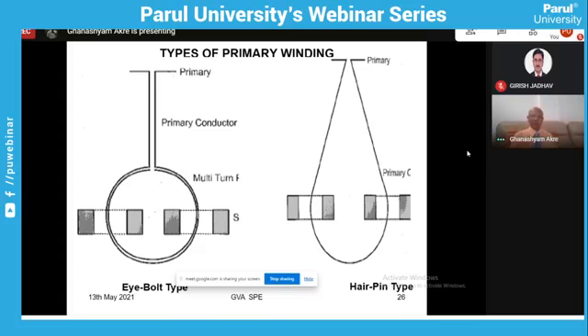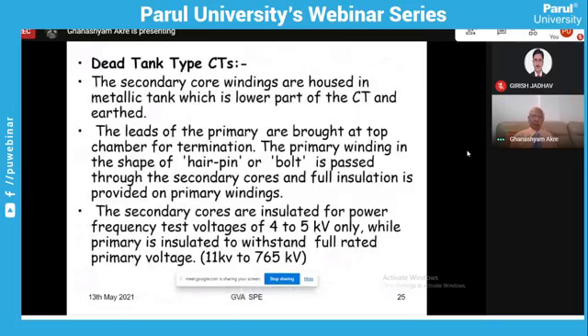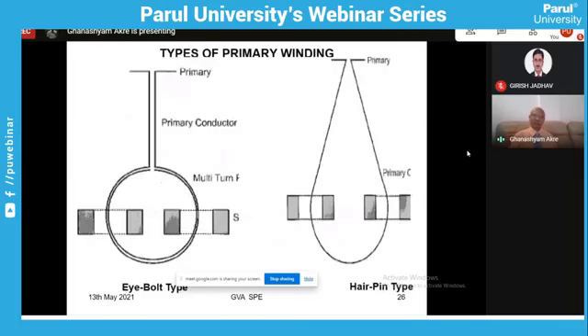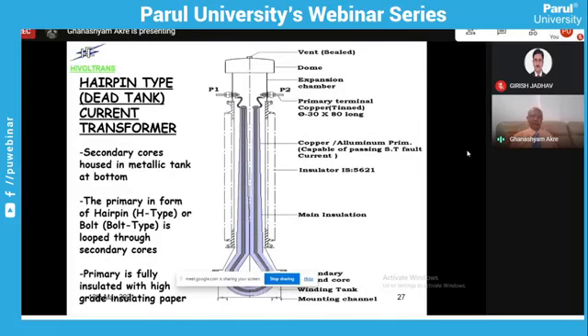And as I explained to you, the principle is that the leads are actually taken down in a bolt or hairpin type, and they are insulated for the high voltage. Here you can see the actual insulation system. This is the hairpin design, and you can see that this is P1 and P2, and this is a primary, either copper tube or aluminum tube, and it is insulated from top to bottom with this insulation. That is the main insulation part you see. It is fully insulated.